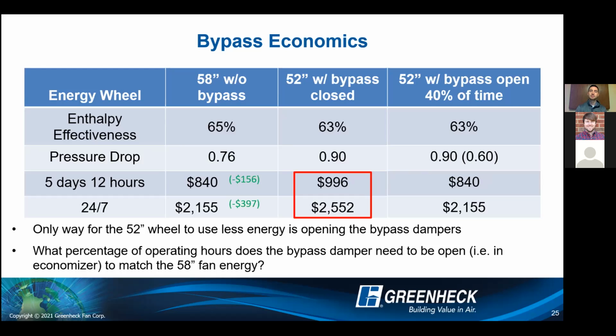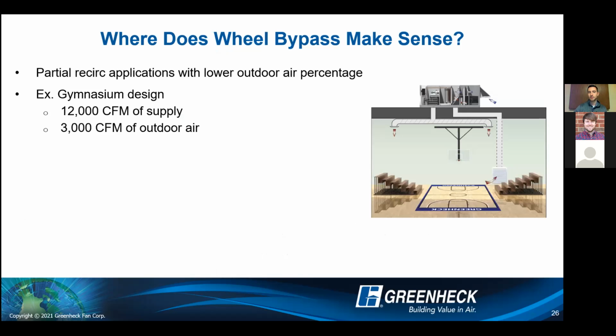sense to actually expand the energy recovery wheel to get as large as possible, increase your effectiveness, reduce your pressure drop during normal operation, and obviously save that fan energy during normal operation versus during economizer. So hopefully that situation makes sense, but that's where our stance is in a DOAS equipment with wheel bypass dampers.